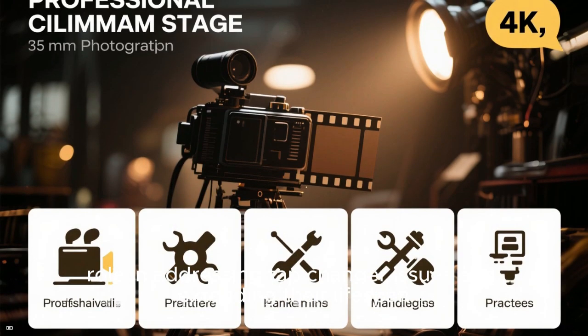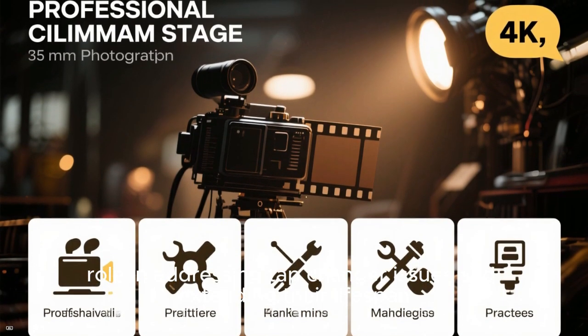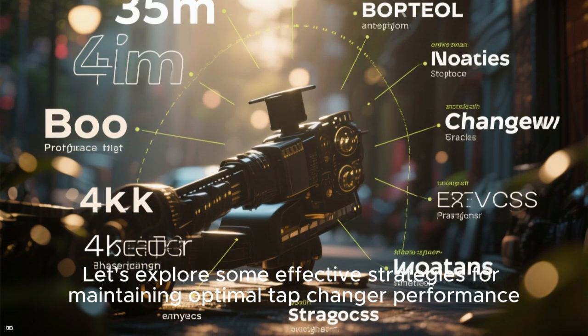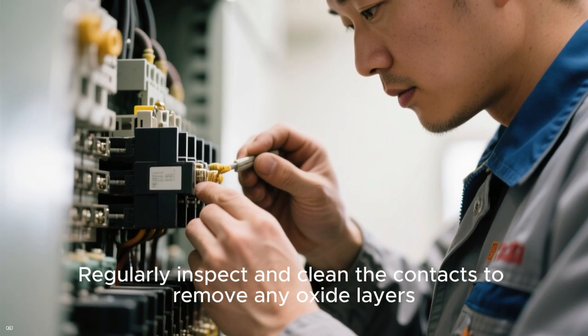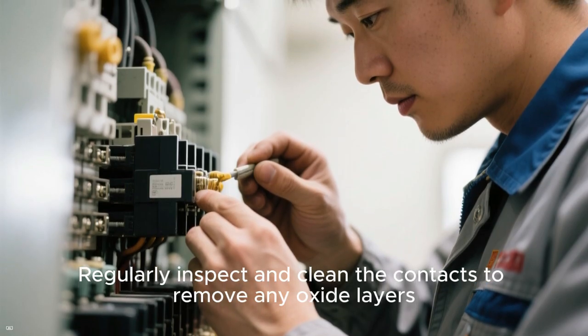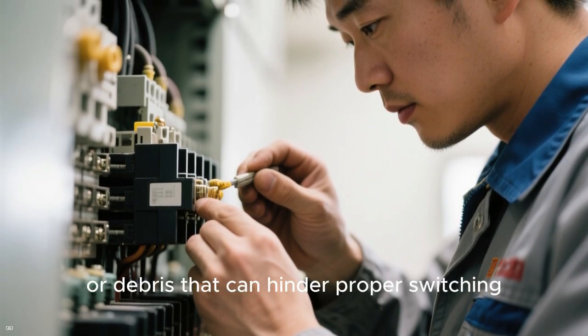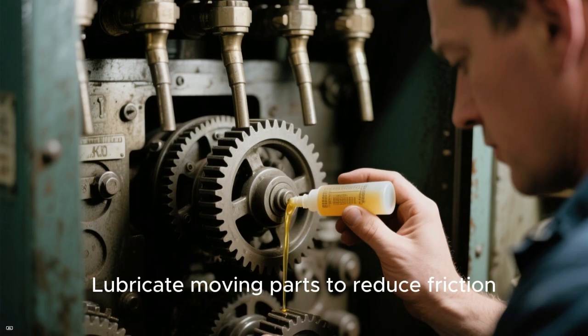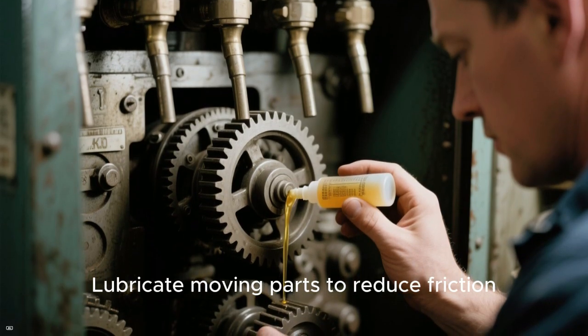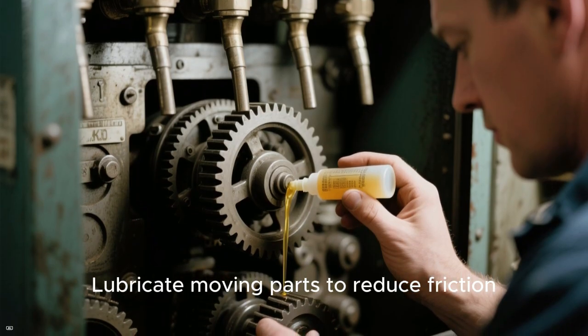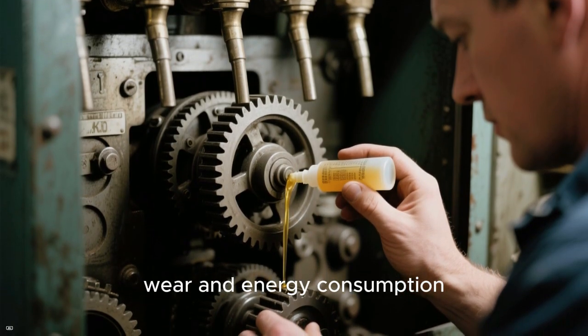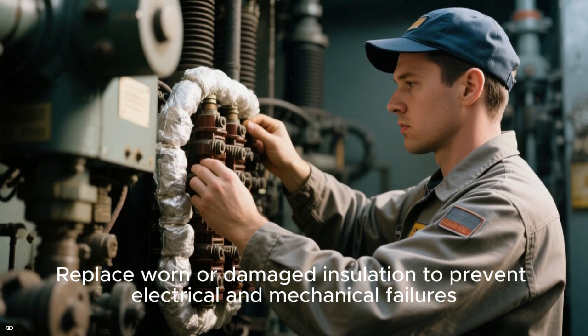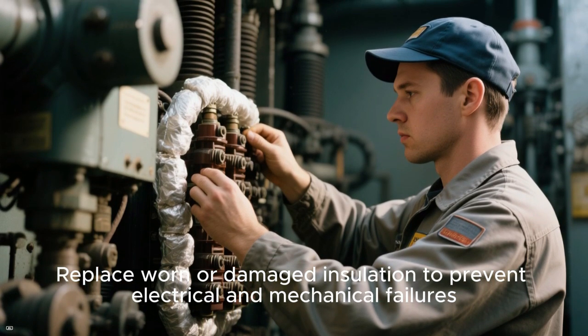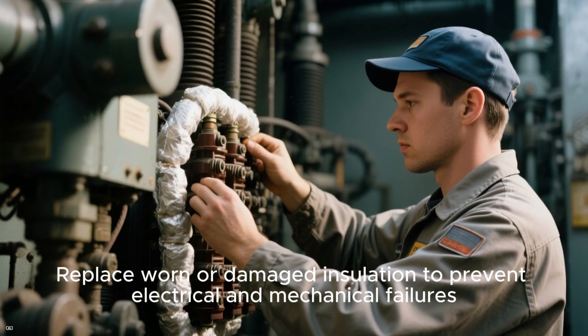Practical maintenance solutions play a pivotal role in addressing tap changer issues and extending their lifespan. Let's explore some effective strategies for maintaining optimal tap changer performance. Regularly inspect and clean the contacts to remove any oxide layers or debris that can hinder proper switching. Lubricate moving parts to reduce friction, wear, and energy consumption. Replace worn or damaged insulation to prevent electrical and mechanical failures.